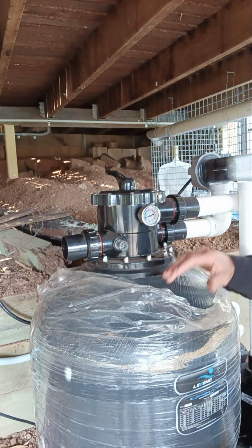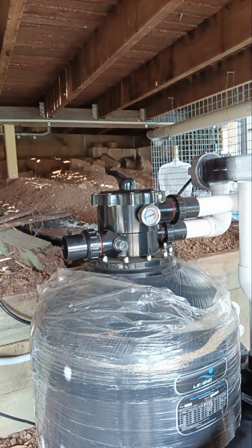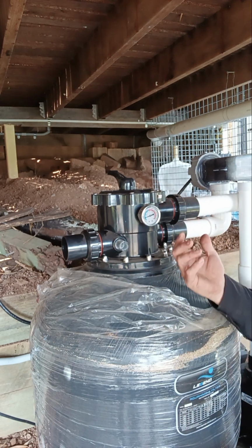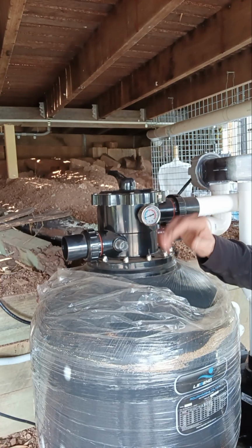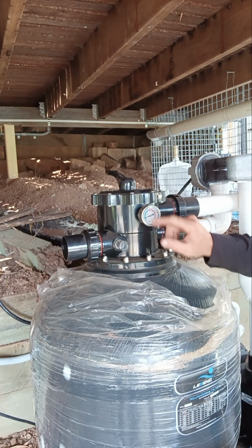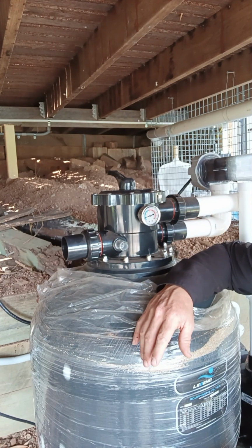Okay, right. So once again, during your weekly or fortnightly visits down here to have a quick look, turn the system off, let it settle, turn the system back on, and then give yourself a nice reading as the most accurate high pressure. Yeah, once it gets above the 100, 150, it's kind of due for a backwash.